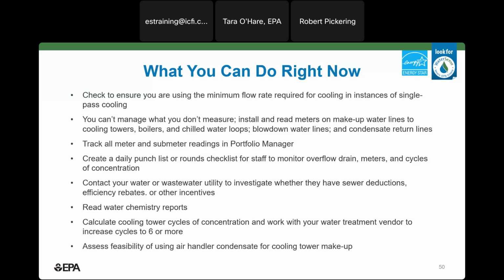Take a minute to review the water chemistry reports that are generated by your water treatment vendor to understand what your current cycles of concentration is, and if your target cycles can maybe be adjusted. If your water chemistry allows, work with your vendor to increase your cooling tower cycles, targeting that 5 or 6 threshold. And then lastly, just take a look at the configuration of your facility to see if there's an easy way to route condensate from your air handlers back to the cooling tower as makeup water. Again, this can be a really pretty simple and cost-effective way to minimize the amount of potable water you're using.